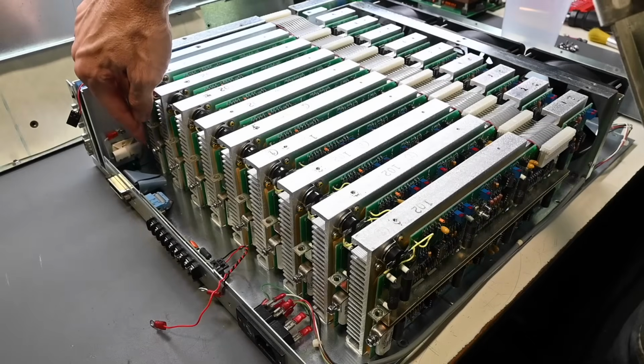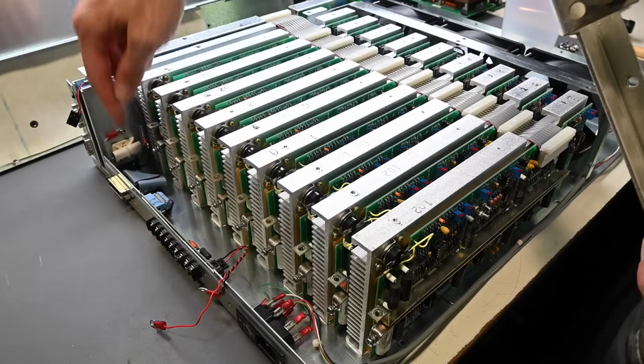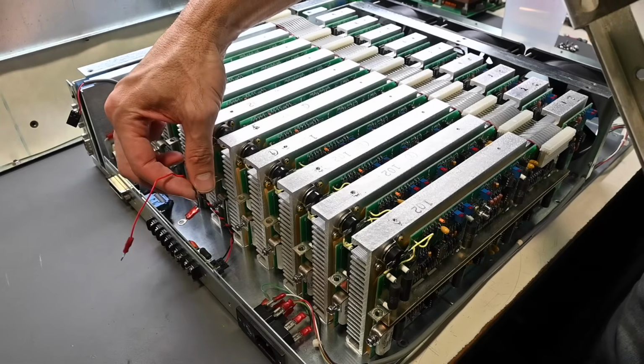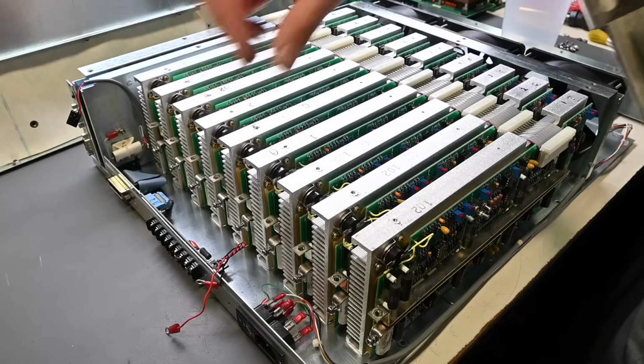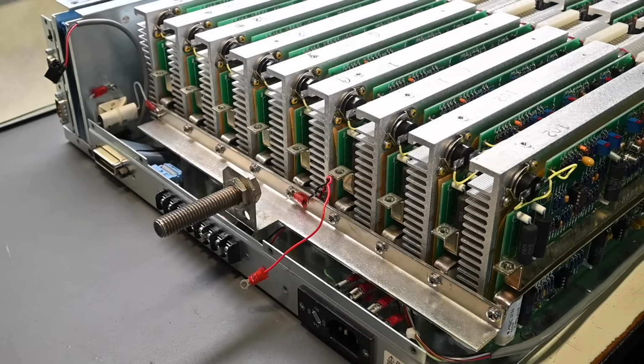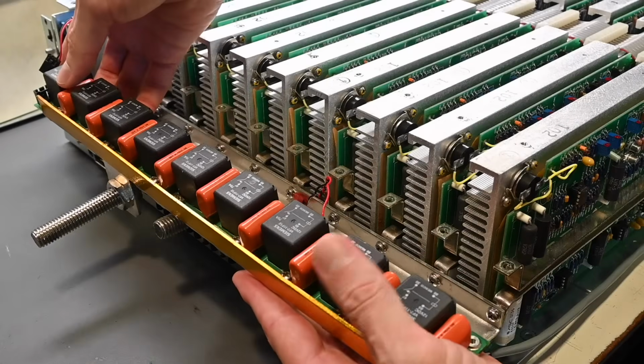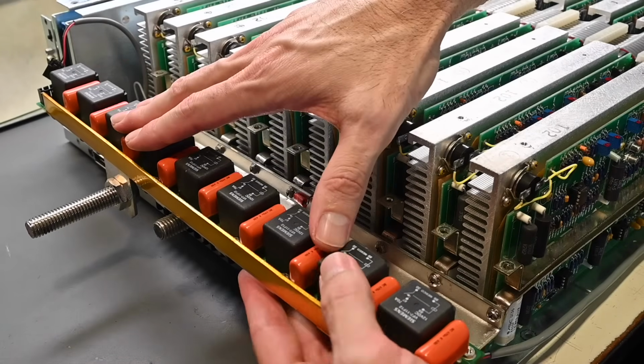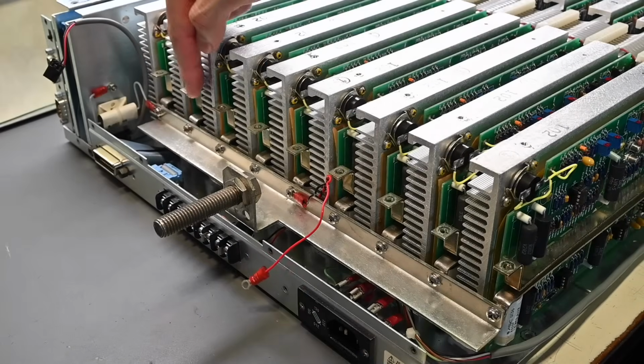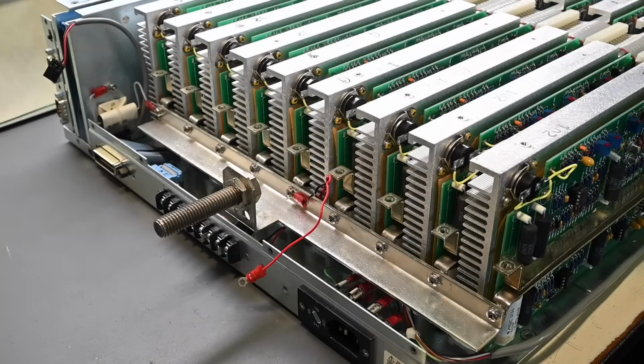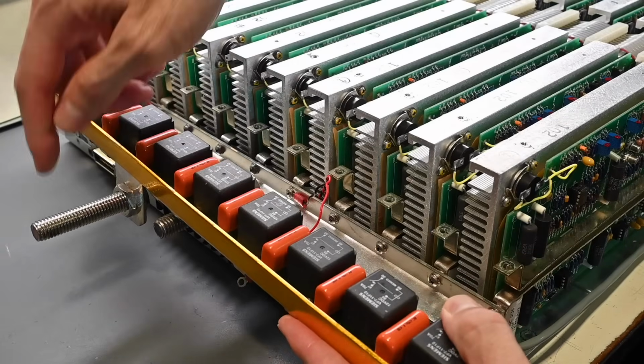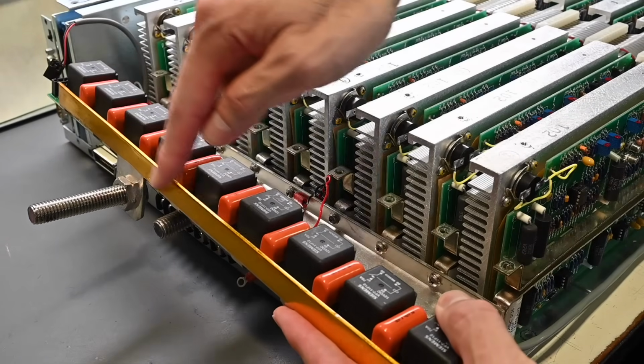This terminal, or the wire right here that comes off of that capacitor, needs to be attached, and the black wire right here also needs to be attached. All right, so the negative bus bar is in place. Now I need to install the positive distribution bus bar, and that's this assembly right here. So this complete assembly attaches to the modules on each of the bus bars off the modules all the way across. And if you look here, you can see the positive input stud attaches to this large bus bar.